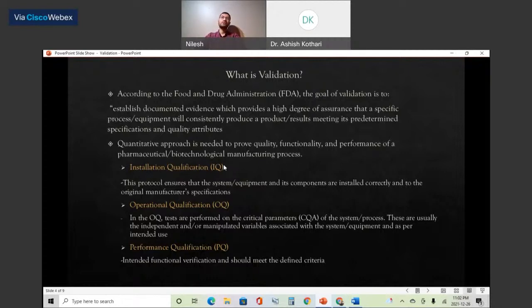Sometimes the vendor will say they'll do the IQ, OQ and PQ. For example, if you buy an HPLC from Agilent or a Waters system, companies that generally provide such equipment will come to your site, install it, do the operational qualification, and do the performance qualification. But they follow a general criteria, a general performance qualification.